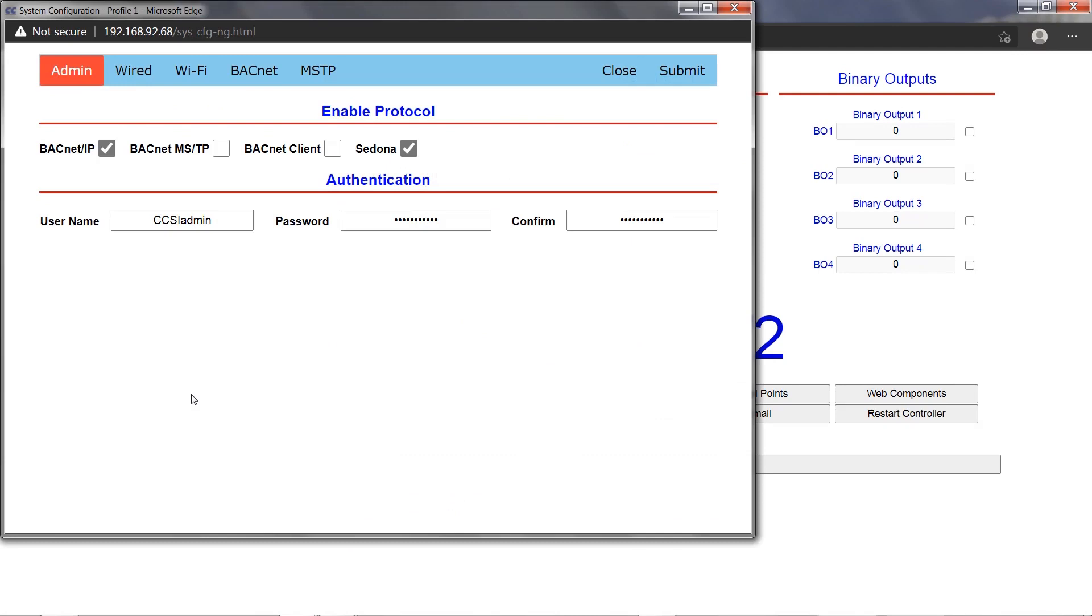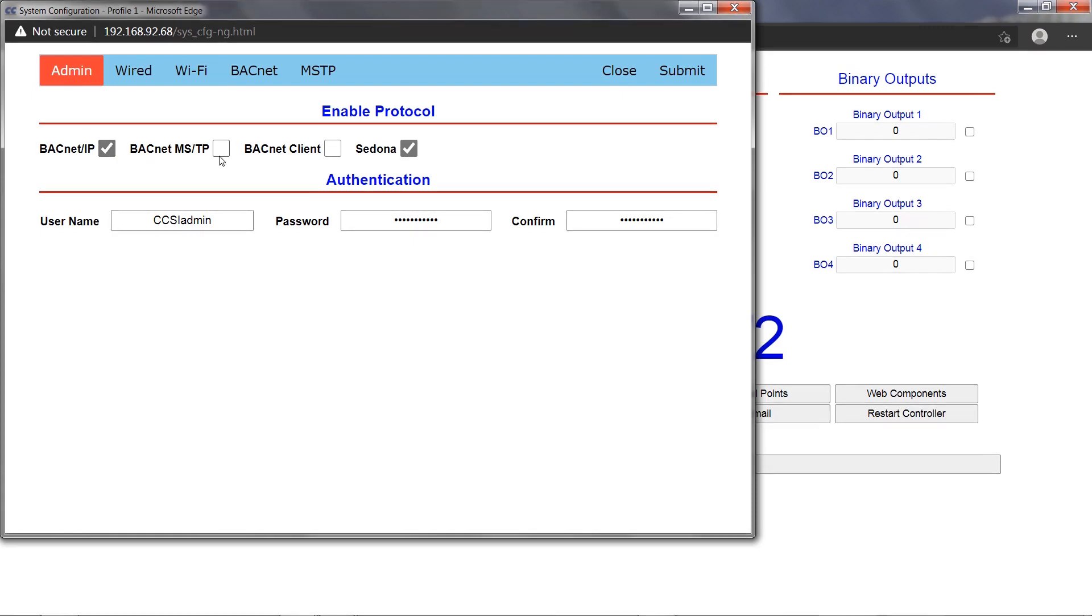The Admin tab allows you to enable or disable protocols supported by the BACnet IP using checkmarks. The BACnet IP checkmark enables or disables the BACnet IP driver and is enabled by default, which enables the BACnet IP server device. The BACnet MSTP checkmark enables or disables the BACnet MSTP driver, which requires an EIA 485 to USB dongle, and this setting is disabled by default.